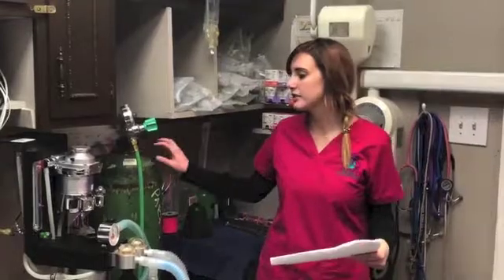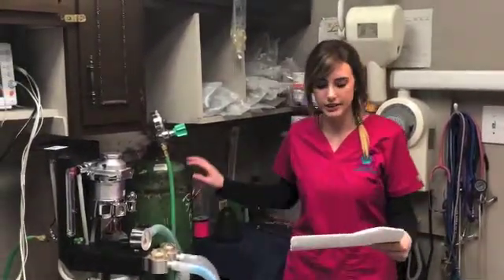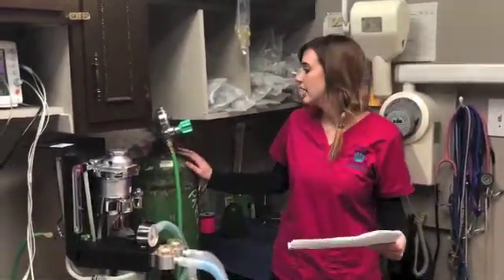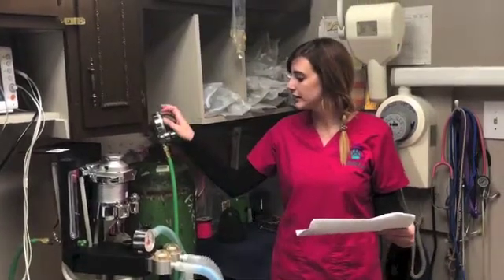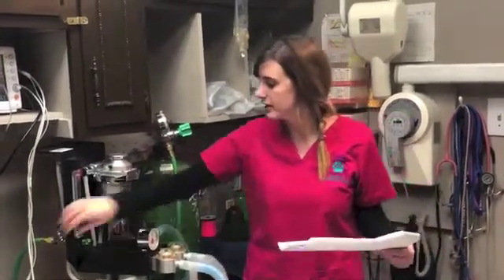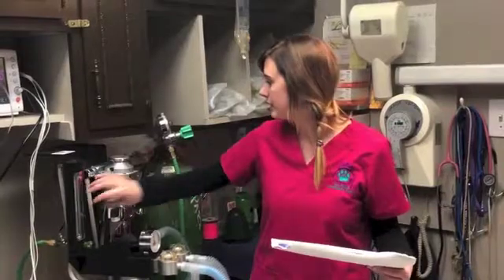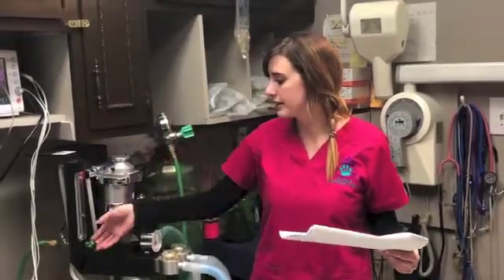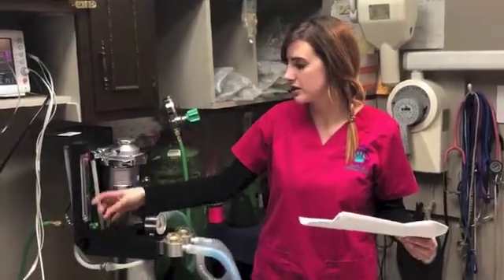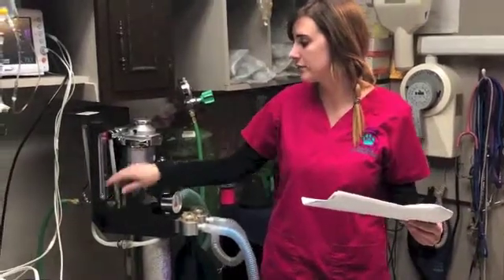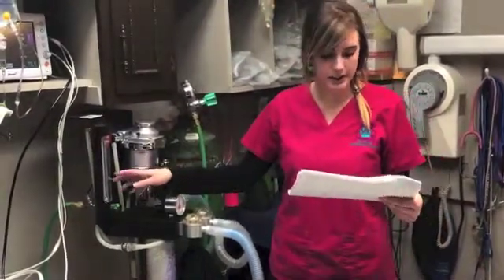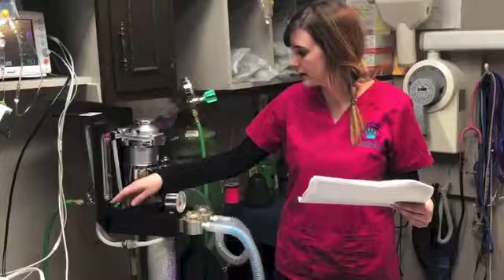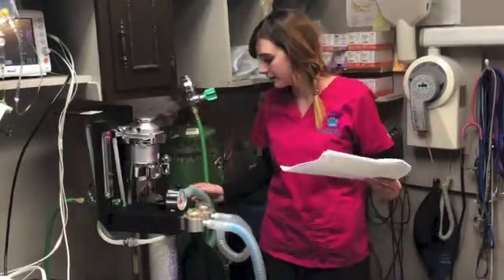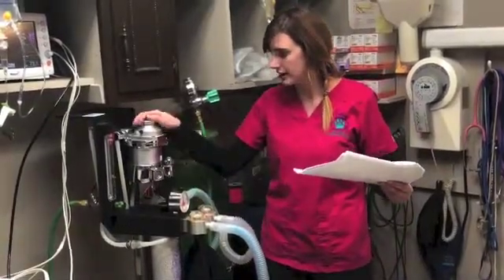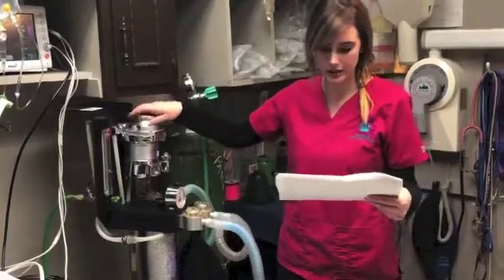I'm going to discuss different parts of our anesthesia machine. This right here is our oxygen tank that flows into our regulator, and then through this green tube flows into the flow meter. The regulator helps with the pressure, and this right here determines how much oxygen you would like your patient to have, and at what level. Then from the flow meter, we have our vaporizer, which is right here, and you can set that on the different setting that you would like it to be on.